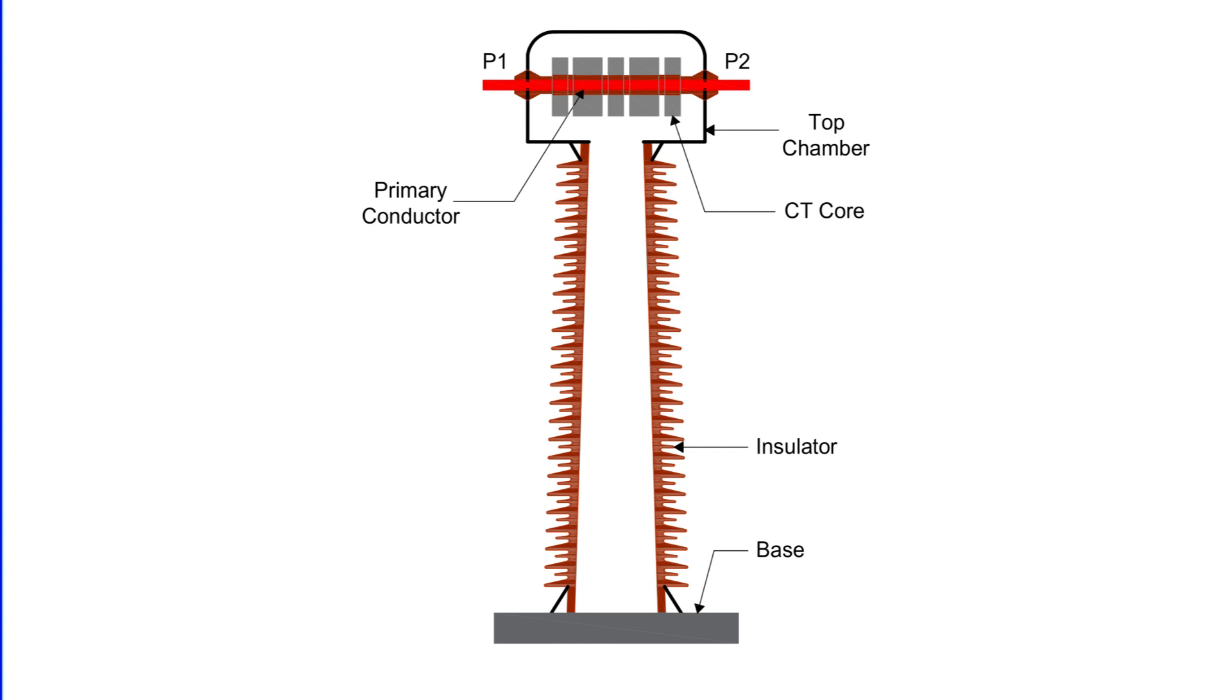This housing is at line potential, not grounded like the dead tank, and the current path is much shorter and more direct. Because of this simpler internal path, there's less insulation stress, less thermal build-up, and less risk of catastrophic failure. Even if something does go wrong, the effects are usually confined and manageable.